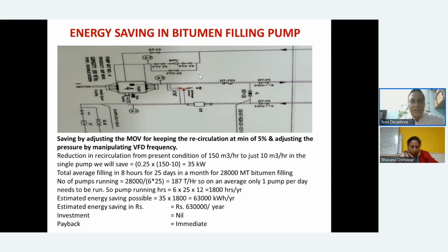So what they did was there was a bypass valve. Initially the bypass valve is open almost, and 150 meter cube is put back. And you know why this is happening in the bypass? Because there are 16 filling stations here for the bitumen tankers, but they come at random, something will get filled up faster, somebody later. So the back pressure will create.